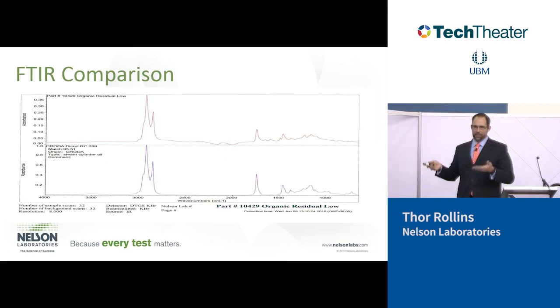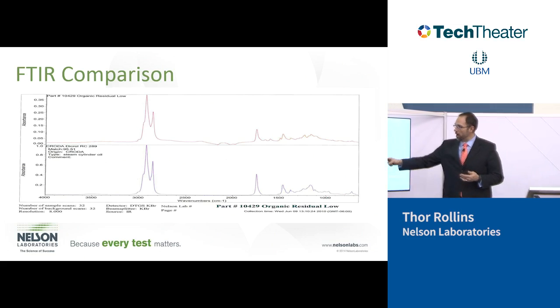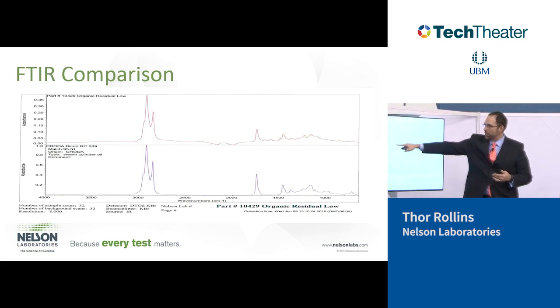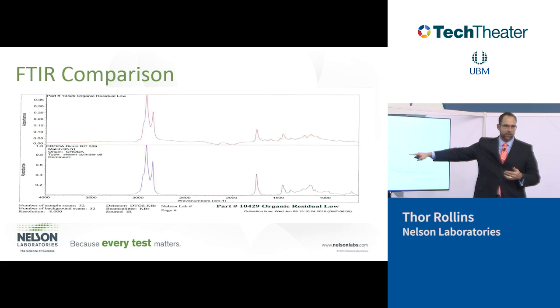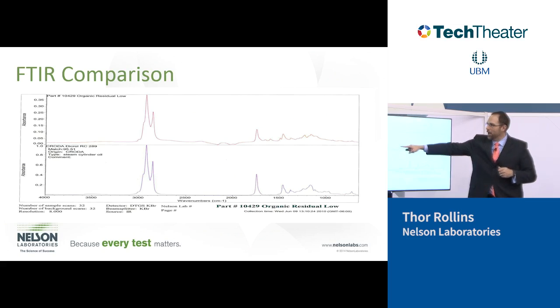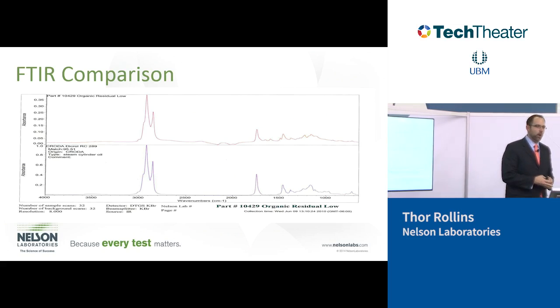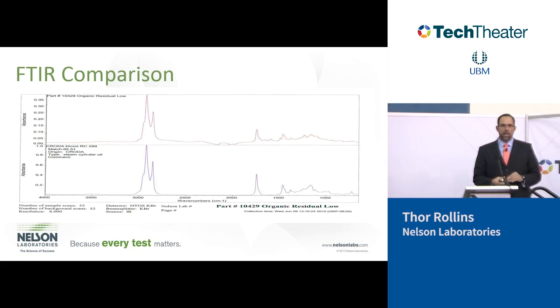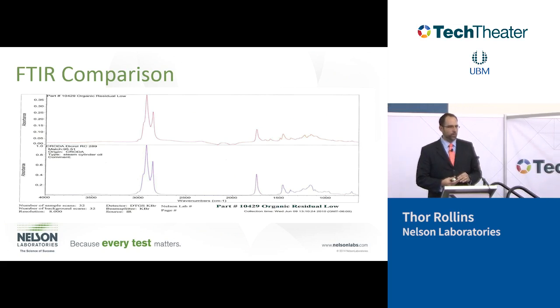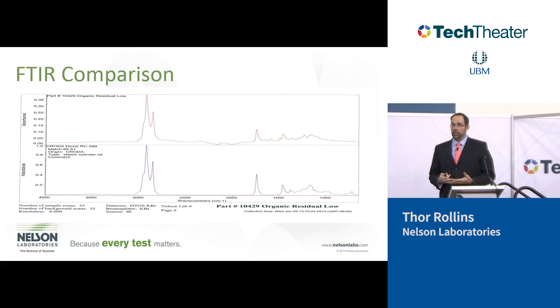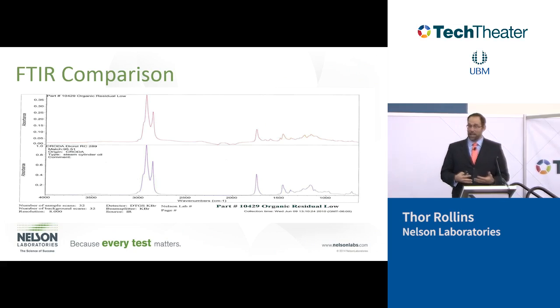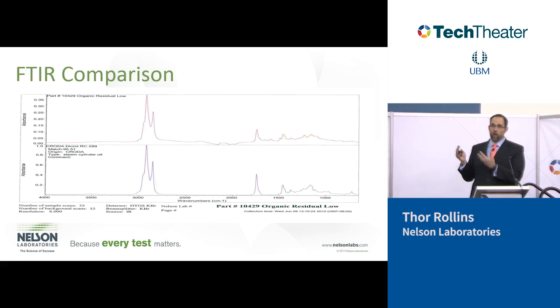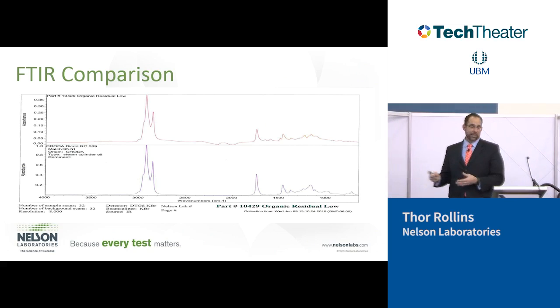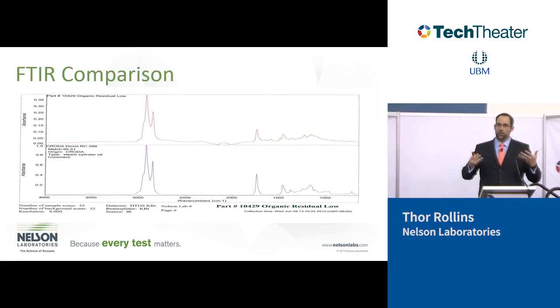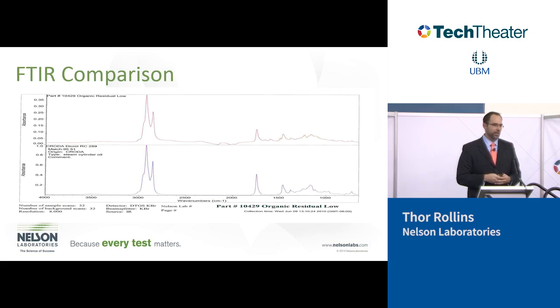But to a chemist, this is like golden. And what you care about is up in the top there, you see that 95.5. You probably can't see it because it's really small, but you can get the presentation like I said. But this has a 95.51% match between these two. Anything over 95%, we consider a good match. So if you're changing a medical device and you want to be able to compare, in a polymer, you can do this, and as long as it's over 95%, that gives you a lot of meat in your justification to be able to show.